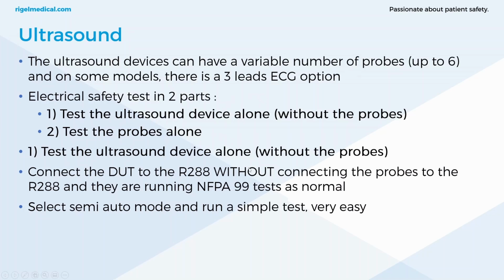So in the first part, connect a Rigel 288 or a safety analyzer without the probes, and we'll just run an NFPA 99 test as you normally would. We select a semi-automatic mode and run a simple test. Now, the reason for this is that the ultrasound devices are potentially power up and power down sensitive, as they're often PC based. So doing an automatic test won't allow time for those load up and shut down times.